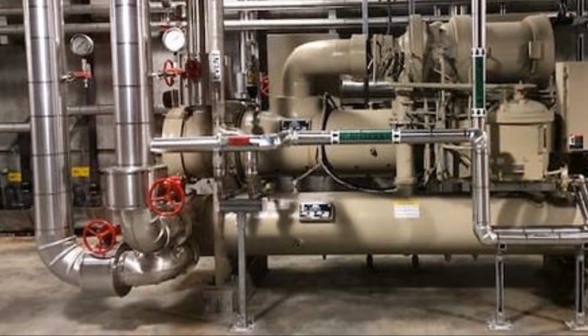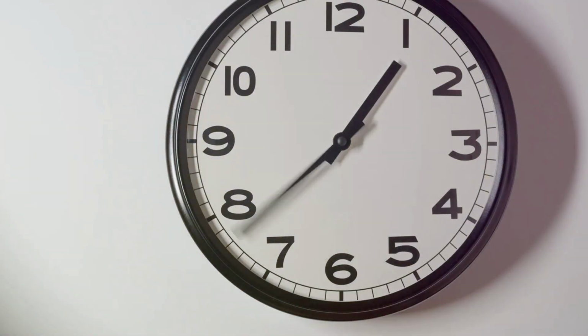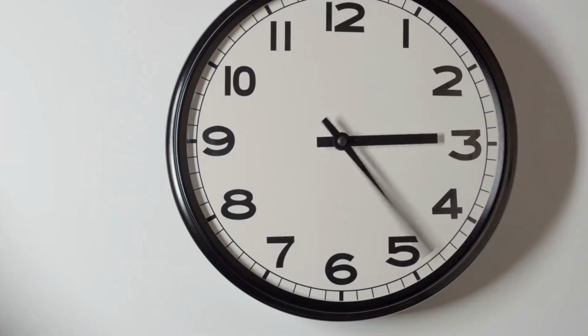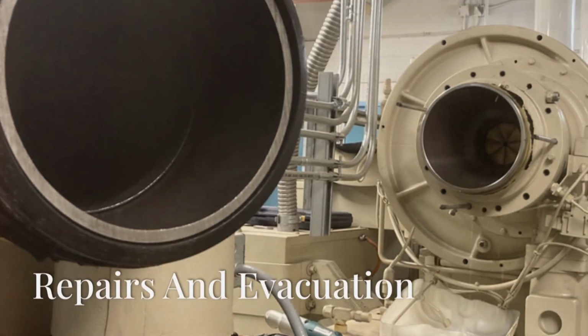After you warm the machine and let it sit for a minimum of 1 to 2 hours with all of the pumps running, then restart the recovery machine. If you have to do all of this multiple times to be 100% certain, then do it. This step is extremely important.